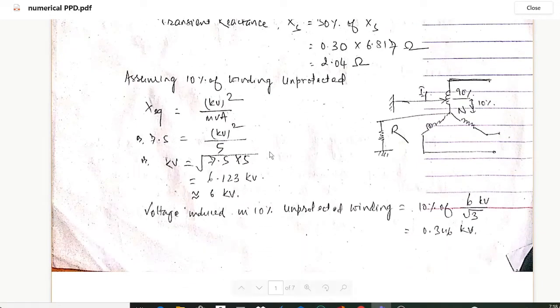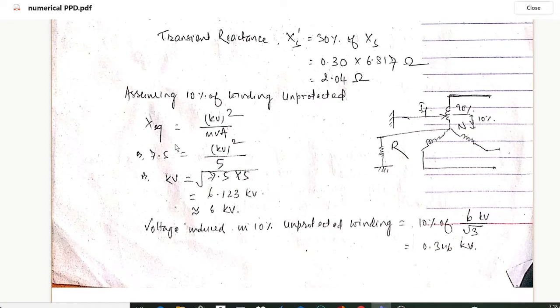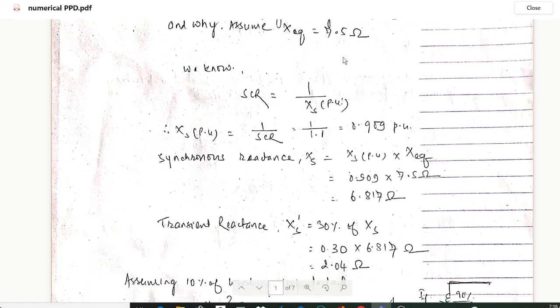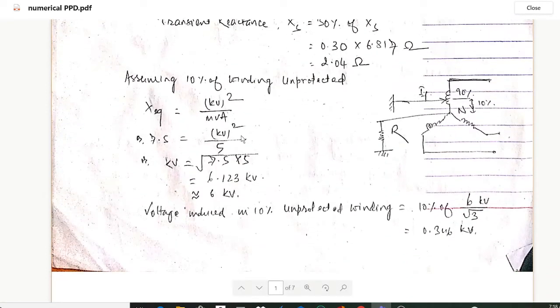Now assuming 10 percentage of winding unprotected, X equivalent will be kV squared upon MVA. X equivalent is 7.5, equal to kV squared upon MVA, and MVA is given as 5 MVA. So kV will be 6.123 kilovolts, and that will be equivalent to 6 kilovolts. Now voltage induced in 10 percentage of unprotected windings: for unprotected windings it will be 10 percentage of Vp, so 6 upon root 3, so we will get 0.346 kilovolts.